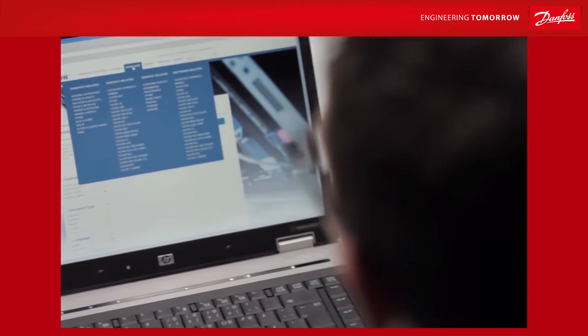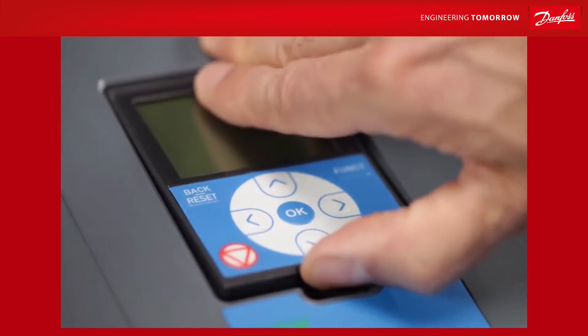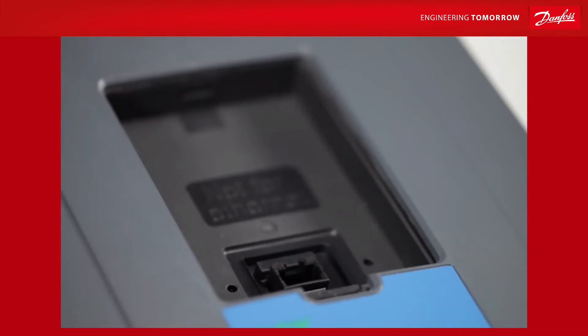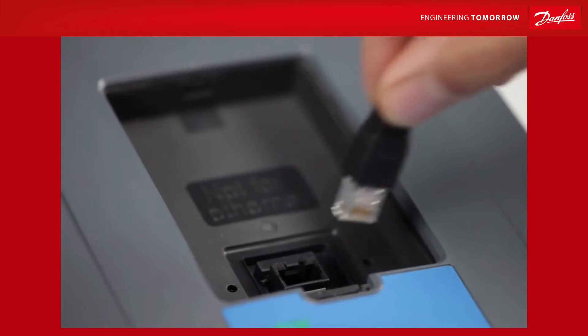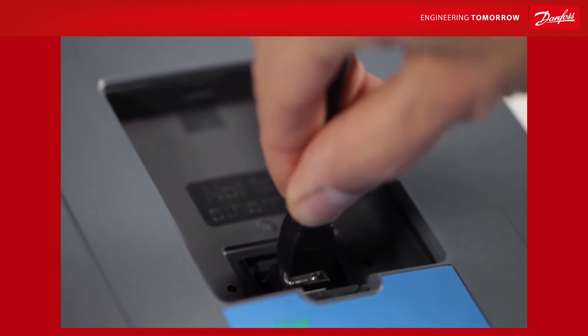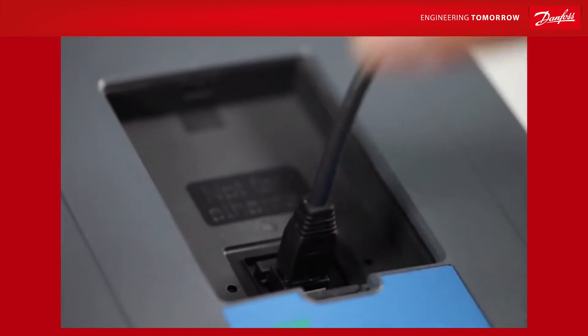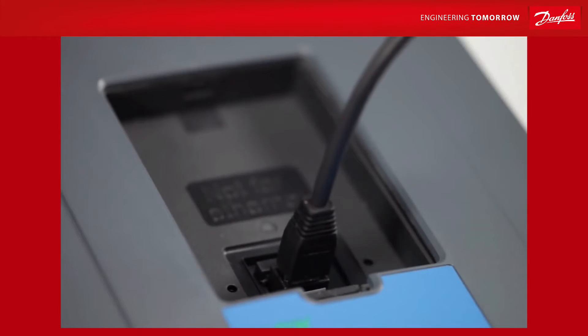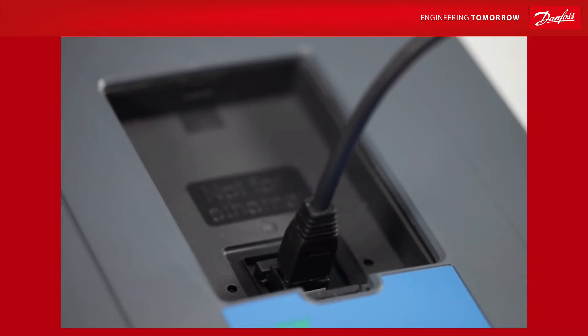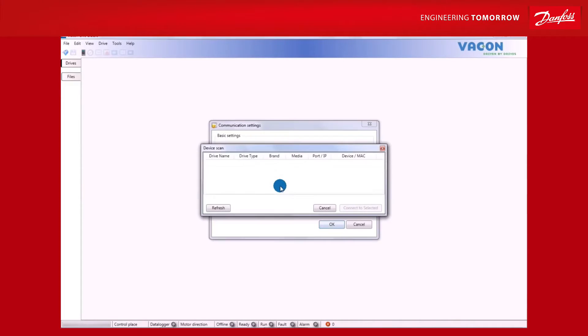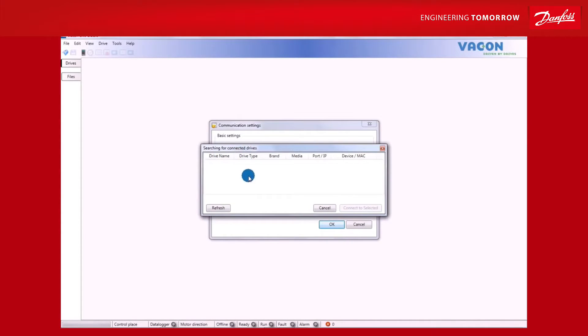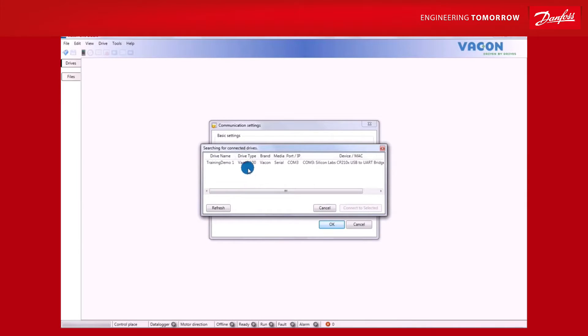To save parameter and monitoring values to your PC, take the following steps. We will assume you have already downloaded VaconLive. Once you've done this, remove the keypad from its slot on the drive and insert the USB-RS-485 cable into the port. In VaconLive, select Online mode and device scanning will start automatically. Once the computer has finished scanning, select a drive from the list.